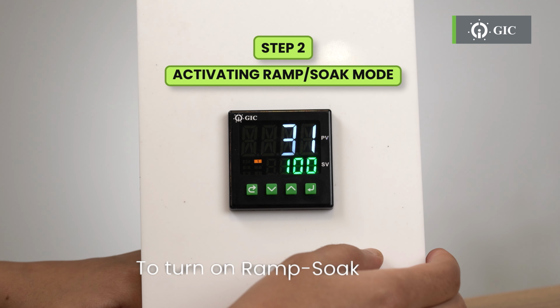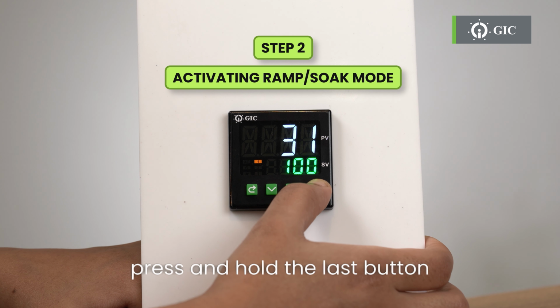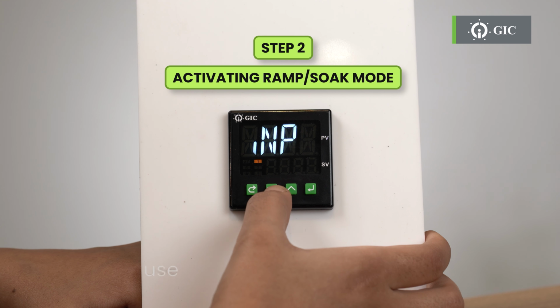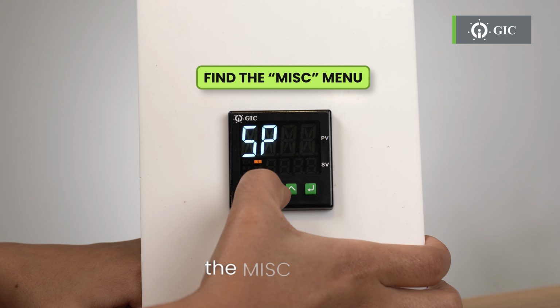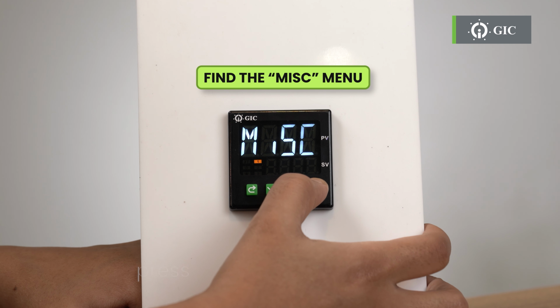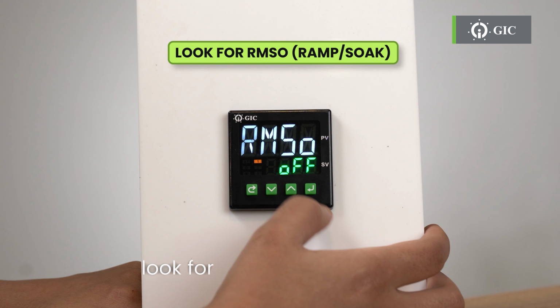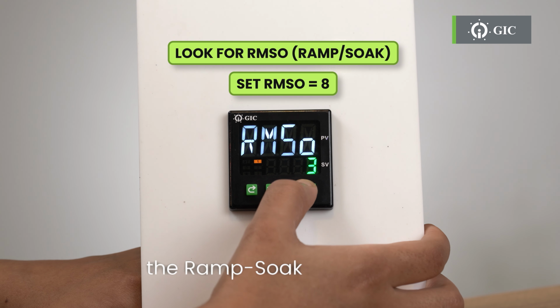To turn on ramp soak mode, press and hold the last button for 2 seconds to open the main menu. Use the up-down key to find the MISC menu, that is miscellaneous. Press the last button to enter. Look for ramp soak and set the ramp soak profile to 8.